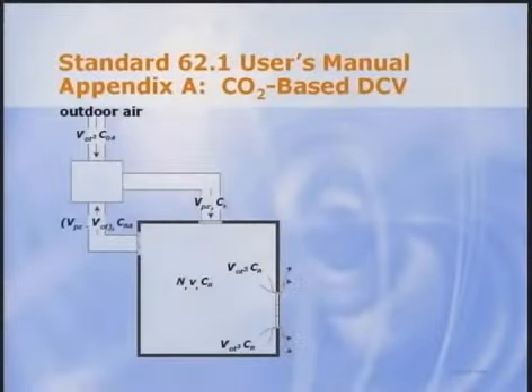The theory behind using CO2 concentration to control ventilation is described in detail in Appendix A of the Standard 62.1 User's Manual for single-zone systems, such as that shown in this schematic. Outdoor air is introduced at the air handling unit, optionally mixed with return air, then supplied to the space. Some of the supply air short circuits to the return if the zone ventilation effectiveness is less than 1, and the rest mixes with the room air. Some room air exfiltrates from the space, while the rest is returned to the air handler.